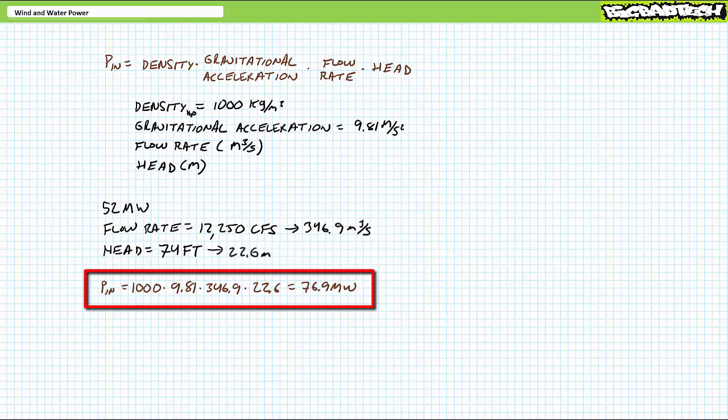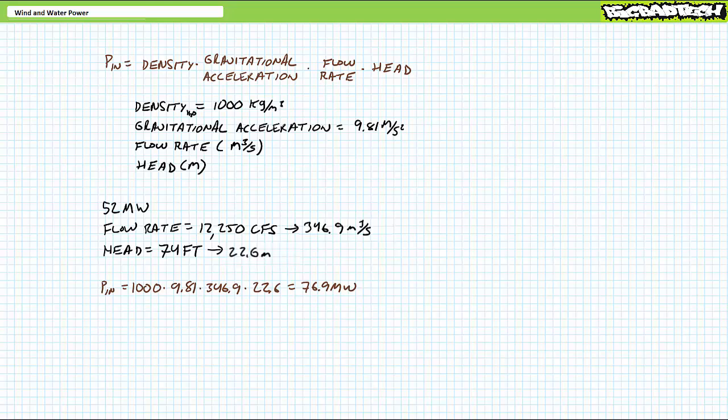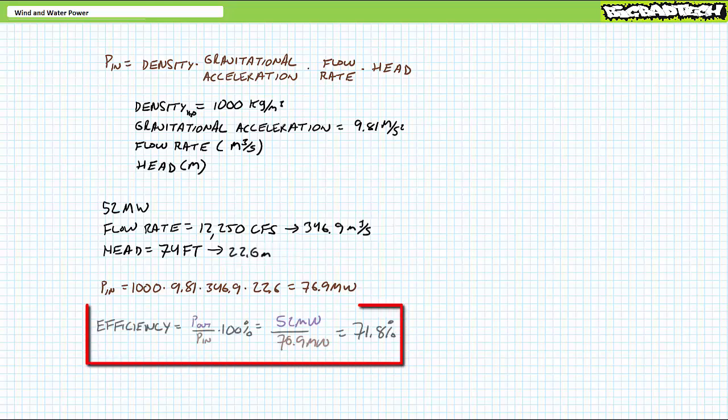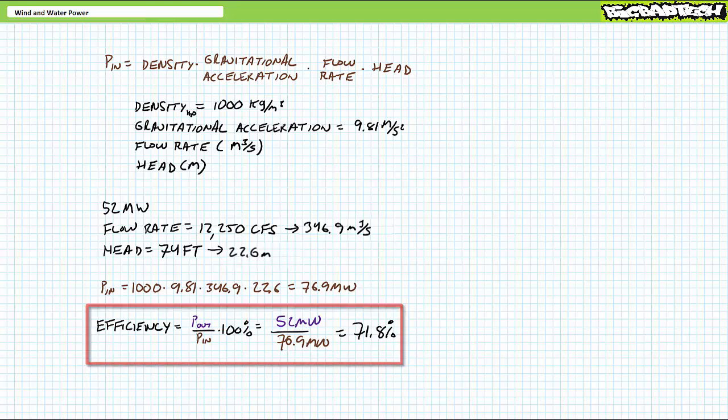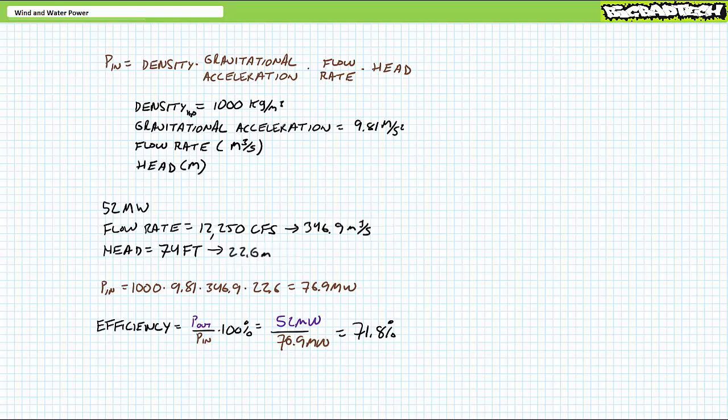Substituting these values into the hydropower equation yields an input of roughly 76.9 megawatts. Given this turbine produces 52 megawatts of usable electrical power output when supplied roughly 76.9 megawatts of hydropower input, this represents an efficiency of roughly 71.8%.